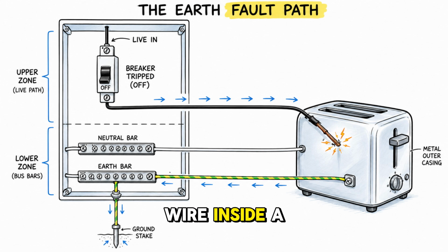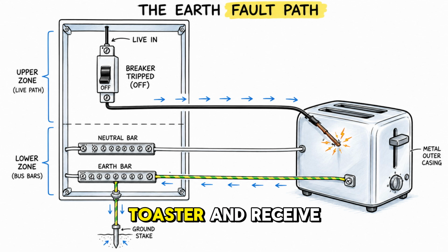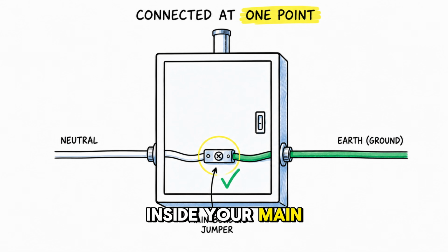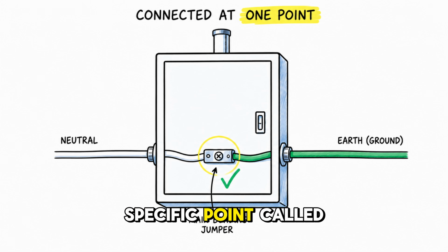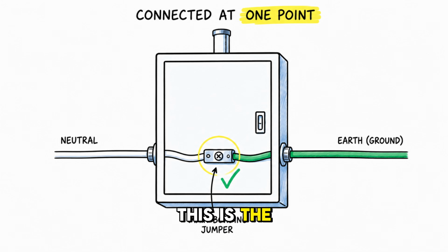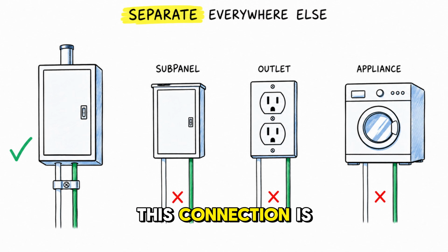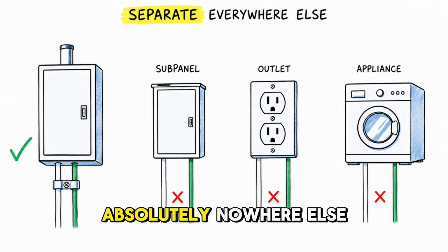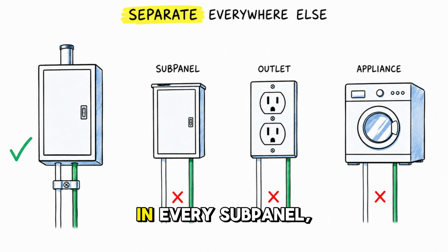If a live wire inside a toaster breaks and touches the metal outer casing, the earth wire carries that dangerous fault current safely away. This massive spike in current trips the circuit breaker before anyone can touch the toaster and receive a shock. Inside your main panel, the neutral and earth are connected together at just one specific point called the main bonding jumper. This is the only place they are allowed to join. This connection is made at the main service panel and absolutely nowhere else. In every subpanel, in every outlet, and in every appliance, they must remain completely separate.